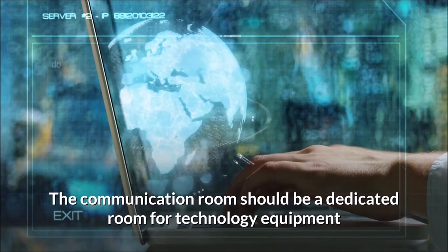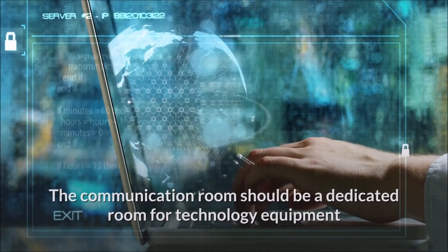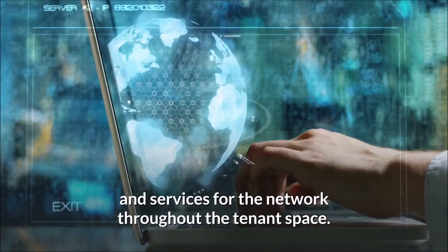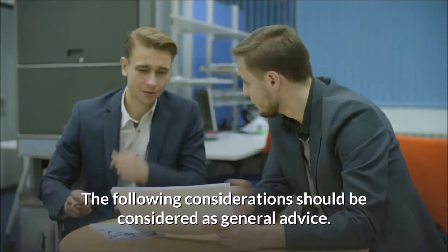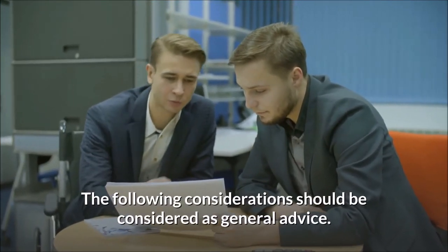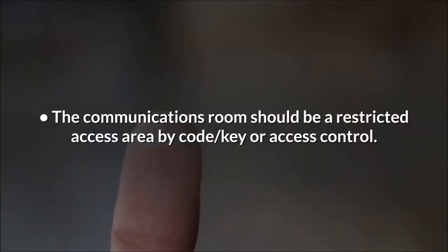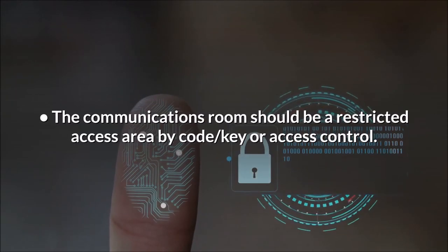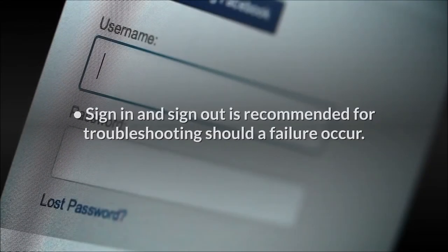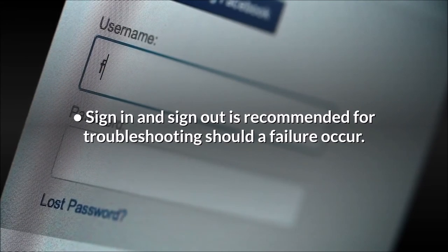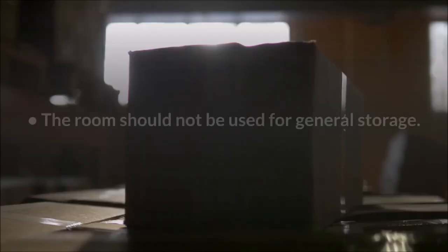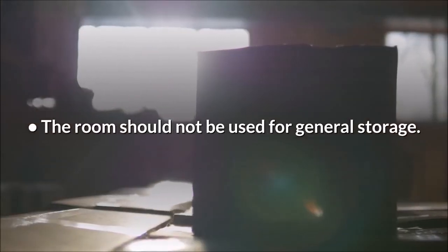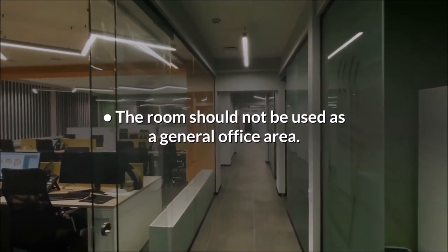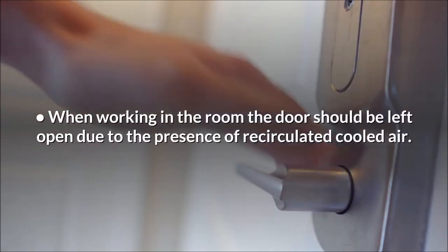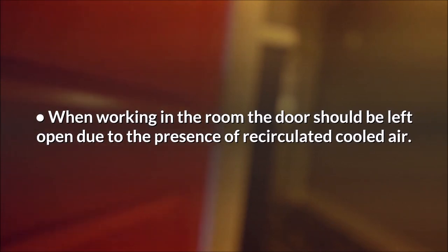Other general considerations for communication room design. The communication room should be a dedicated room for technology equipment and services for the network throughout the tenant space. The following considerations should be considered as general advice. The communications room should be a restricted access area by code, key or access control. Sign in and sign out is recommended for troubleshooting should a failure occur. The room should not be used for general storage. The room should not be used as a general office area. When working in the room, the door should be left open due to the presence of recirculated cooled air.